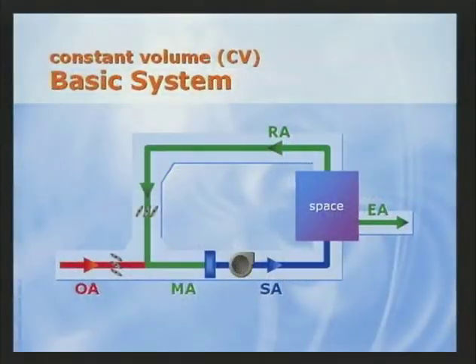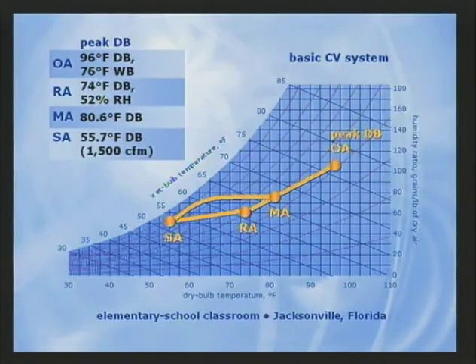Now, this is a schematic of that basic single-zone constant volume system. It supplies a constant quantity of air to a single classroom. A thermostat compares the dry bulb temperature in the space to a set point. It then modulates the capacity of the cooling coil until space temperature matches this set point. At the traditional peak dry bulb design condition, when the outdoor air is the warmest, this basic constant volume system can control space dry bulb temperature to the desired set point and maintain relative humidity at an acceptable level, 52% for our example classroom. So what about at part load conditions?